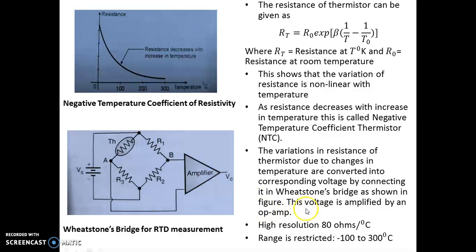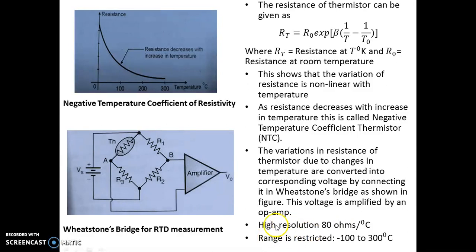Thermistor has very high resolution — in contrast with PRT, for each degree Celsius change in temperature the resistance of a thermistor varies by 80 ohms, which is very high compared to only 7 ohms for PRT. However, the temperature range is restricted for thermistor — it is from minus 100 degree Celsius to 300 degree Celsius, which is a limitation of thermistor.